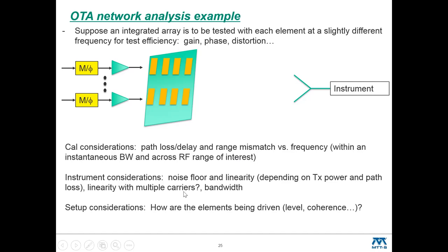So some of the calibration considerations: what are the path losses? We talked about that. And what are the mismatch levels, say, of this device or of the instrument? You can work those against each other, and that'll help you determine how significant a calibration you're going to need.